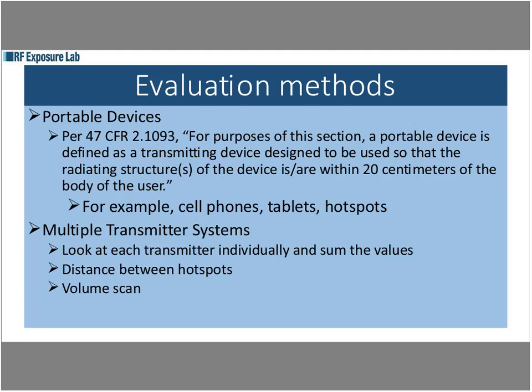Basically, you do an area scan across all of the antennas so that you cover the full area of both, or however many antennas there are. And you do that for each of the different transmitter bands that gives you the highest numbers. It actually does more like a zoom scan or a cube scan, where it does the area, but it does multiple, 7 or 8, measurements coming out of the tissue at each and every point. Once that's completed, you take all of the data from the multiple transmitters and sum all of those separate points within the two measurements. At each individual point, you sum up all the values, and then you reevaluate what the SAR value would be overall with two transmitters operating at the same time.